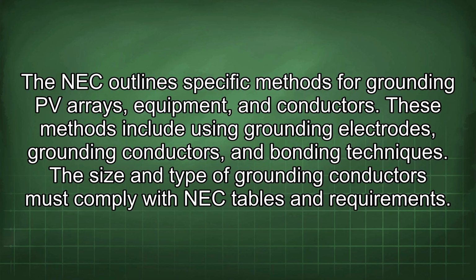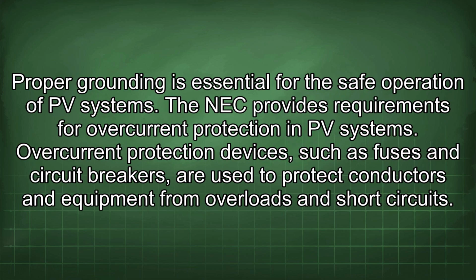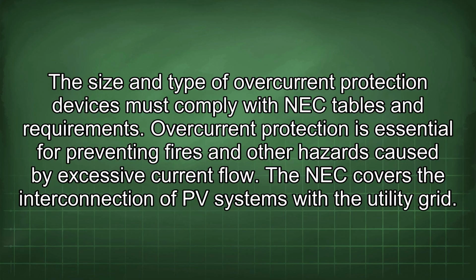The NEC outlines specific methods for grounding PV arrays, equipment, and conductors. These methods include using grounding electrodes, grounding conductors, and bonding techniques. The size and type of grounding conductors must comply with NEC tables and requirements. Proper grounding is essential for the safe operation of PV systems. The NEC provides requirements for overcurrent protection in PV systems. Overcurrent protection devices such as fuses and circuit breakers are used to protect conductors and equipment from overloads and short circuits. The size and type of overcurrent protection devices must comply with NEC tables and requirements. Overcurrent protection is essential for preventing fires and other hazards caused by excessive current flow.